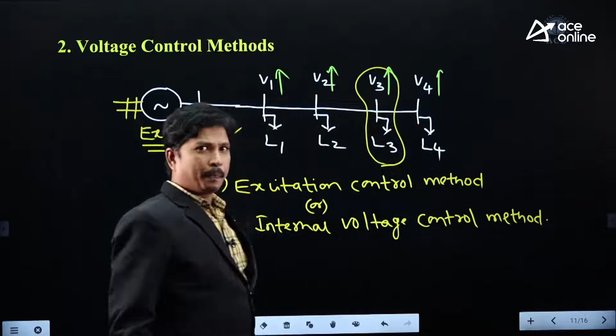Right? Whenever the excitation of the generator is varied to vary the voltage at any bus, that excitation is varying all the bus voltages, which is not at all required for me. Right? I want to control the voltage at only a particular bus, but whenever you control the excitation, it changes the voltages of all the buses.